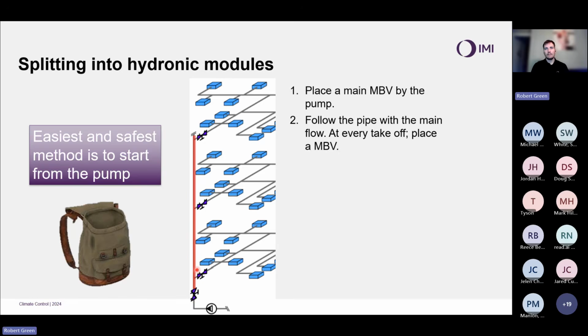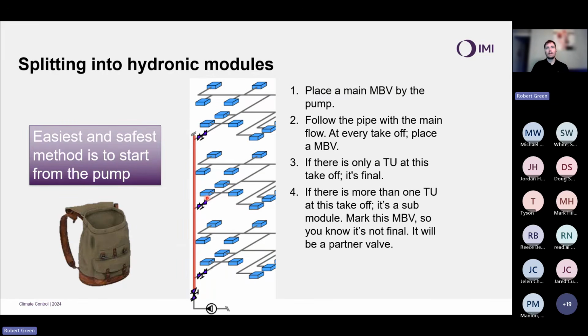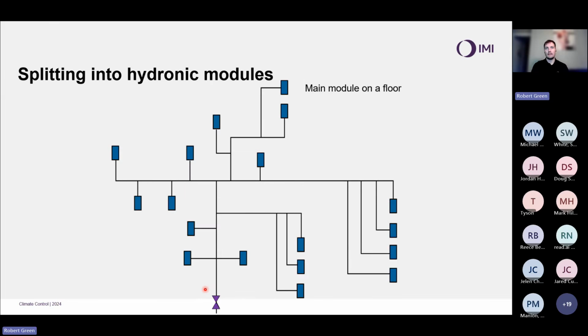We then say, if there is only a terminal unit at that takeoff, that's final. So if that up here was serving a single air handling unit, that's final. We don't need to do any balancing downstream of that unit because all there is is that particular air handling unit. But if there's more than one terminal unit at this takeoff, we designate it as a sub-module. And we mark this manual balancing valve so we know it's not final and we know it's a partner valve. The safest method is always to do this process starting from the pump, methodically following the path of the main flow, placing a balancing valve and carrying on up the system, and marking those balancing valves where you need to go and revisit. And you take that exact same process in this example on a floor.